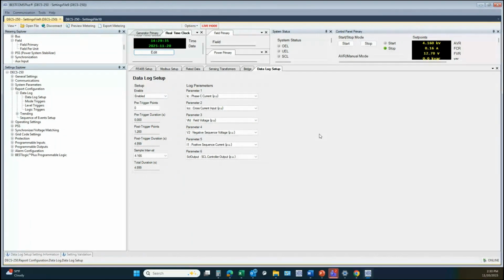And again, all of our software is free to download, but when saving the data logs as ComTrade files from the DECS, then our BESTwave software can be used to open and view those ComTrade files. The data logs can also be downloaded as a log file, which you can use software like spreadsheet software to open those log files and graph it out within the spreadsheet software. So the pre-trigger points is how many data points do you want recorded before the actual event occurs, and then the post-trigger is how many will be recorded after the event occurs.